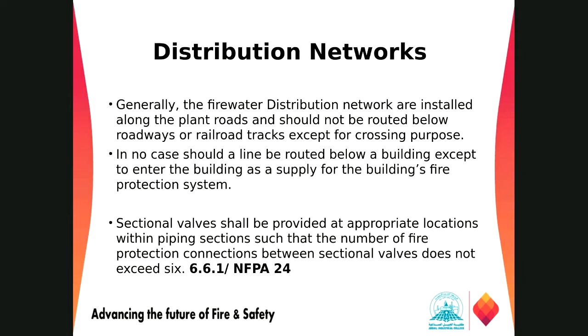In most cases, fire water networks are installed along the plant road, right? They never cross the road, or we are not allowed to cross the road unless it is necessary, right? If it is not necessary, or in case of maintenance, we have some difficulties, or you have to bury the pipe below 1.2 meters of ground if it is some heavy road, a vehicle access road, or maybe trucks and all those things can put heavy loads on those fire protection equipments.